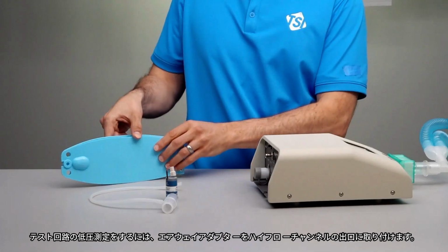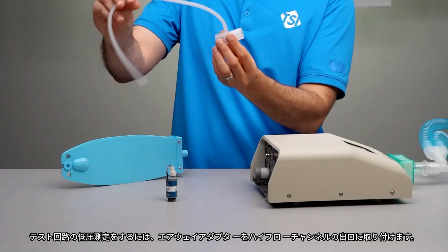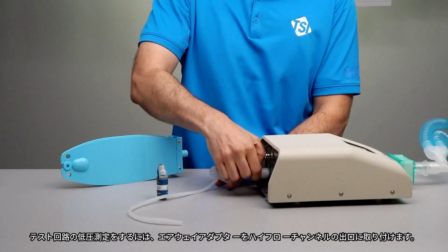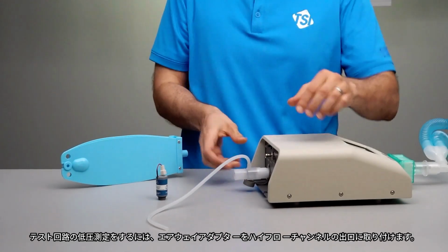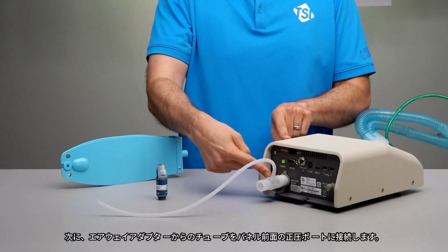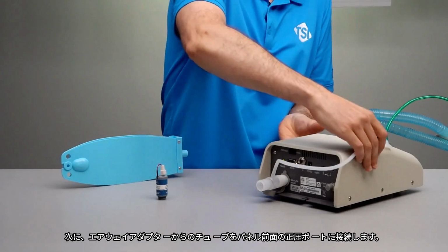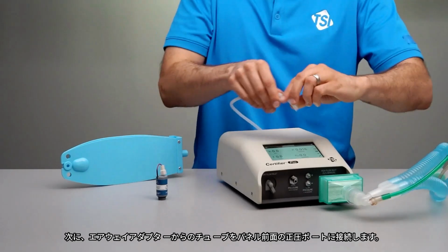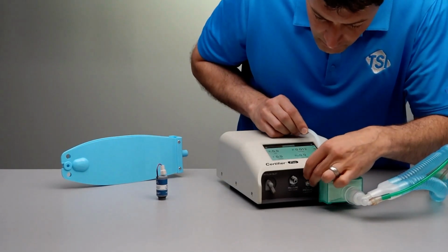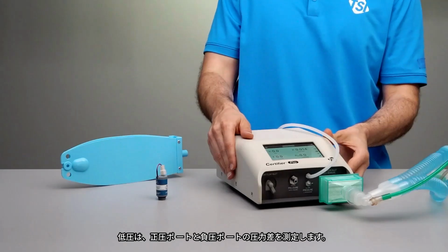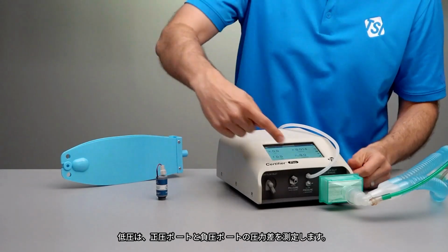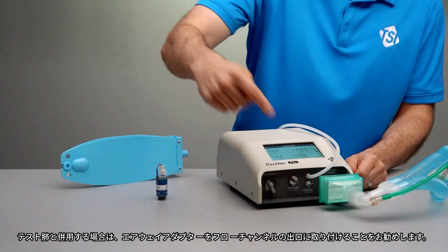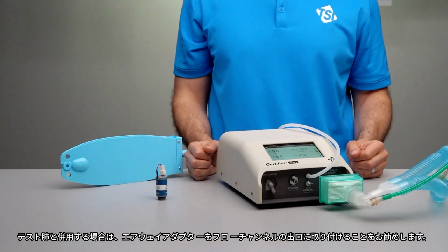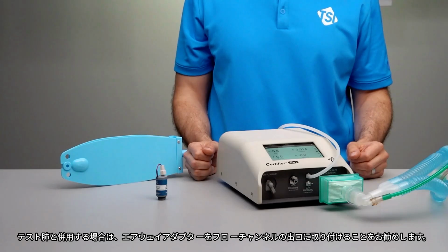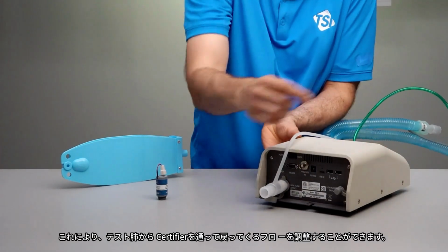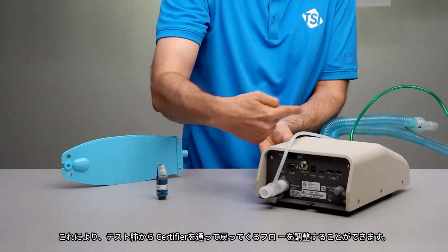To connect the low pressure measurement to the test circuit, attach the airway adapter to the outlet of the high flow channel, and then connect a piece of tubing from the airway adapter to the positive port on the front of the panel. Low pressure measures the difference in pressure between the positive and negative pressure ports. When used with a test lung, we recommend that the low pressure adapter be placed on the outlet of the flow channel, as this will help to condition the flows coming back from the test lung through the certifier.